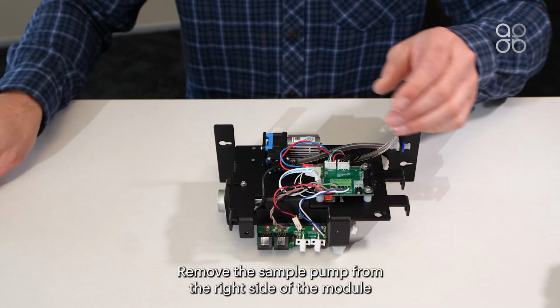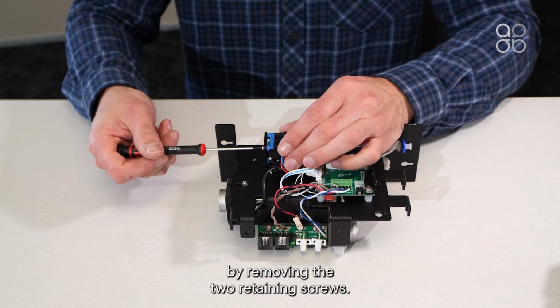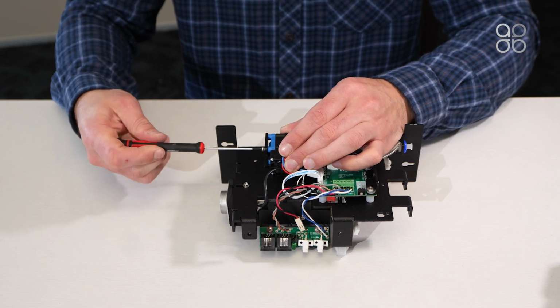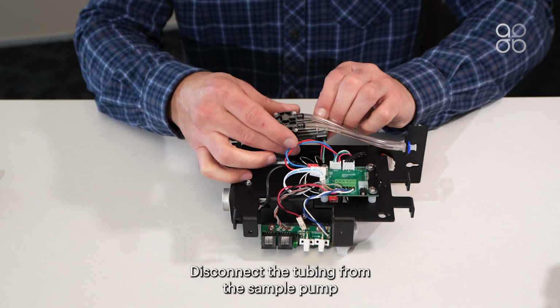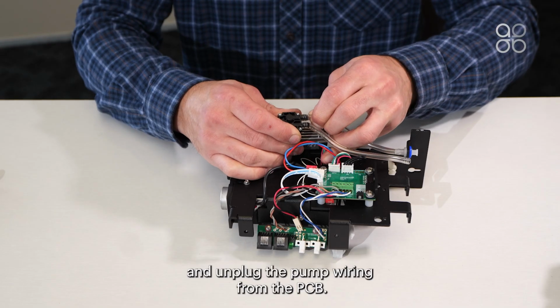Remove the sample pump from the right side of the module by removing the 2 retaining screws. Disconnect the tubing from the sample pump and unplug the pump wiring from the PCB.